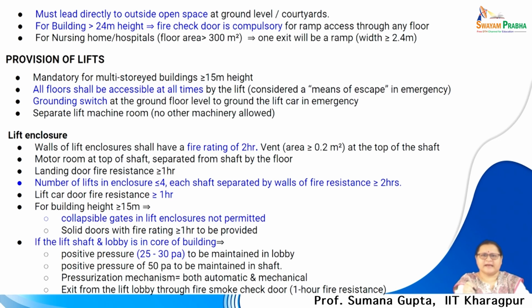Provision of lifts: as you have understood, we also need a lift to negotiate height. Beyond say 50 meters, it is very difficult for people to come down, and as more people flow outside the building, the staircase becomes more and more crowded. So, provision of a lift is mandatory for multi-storied buildings beyond 15 meter height, but beyond 24 meters the fire lift or the fire tower is mandatory, which, to reiterate, is a staircase, a lift as well as a pressurized lobby space.